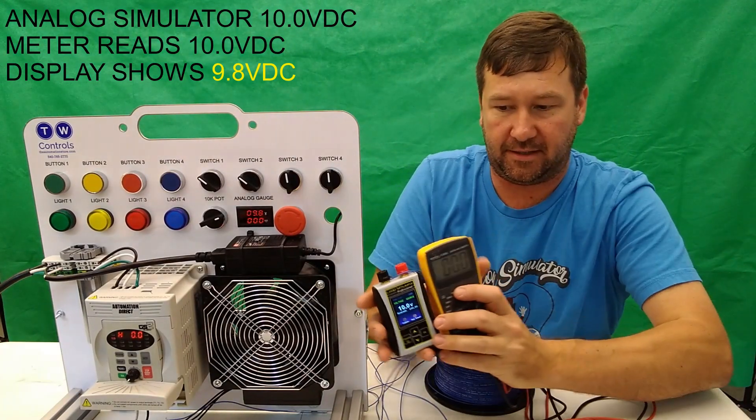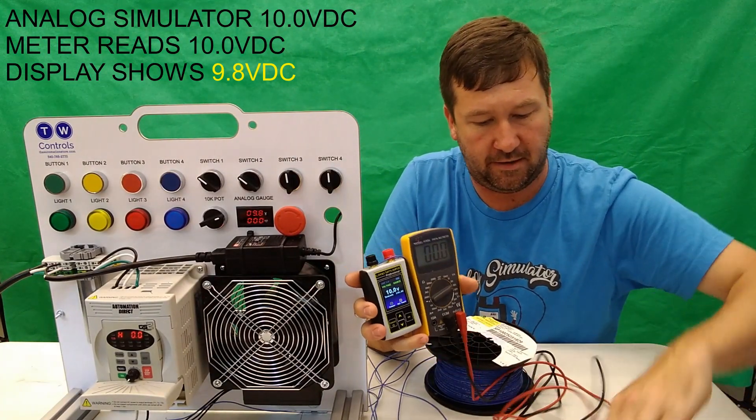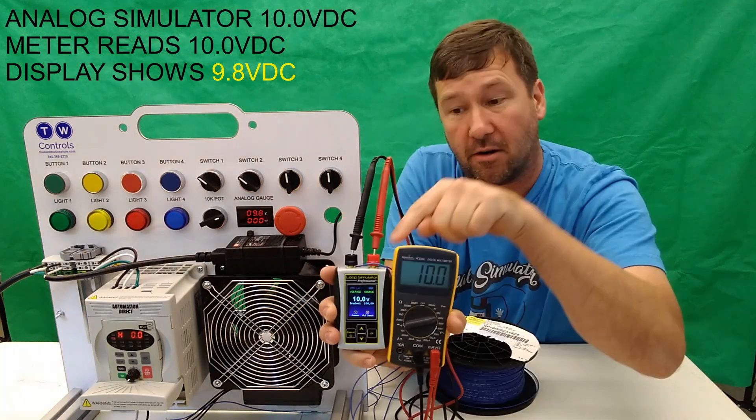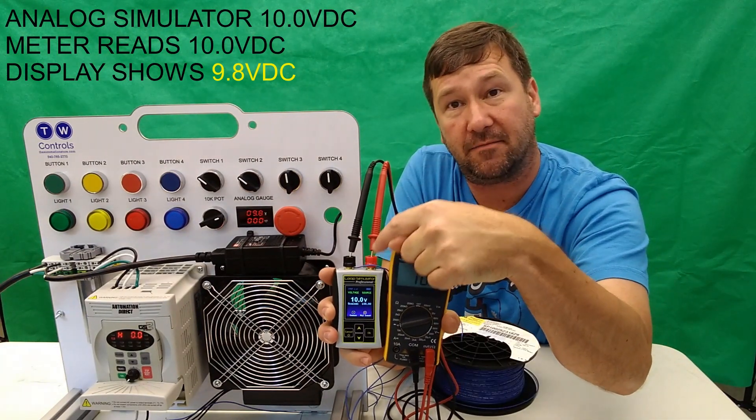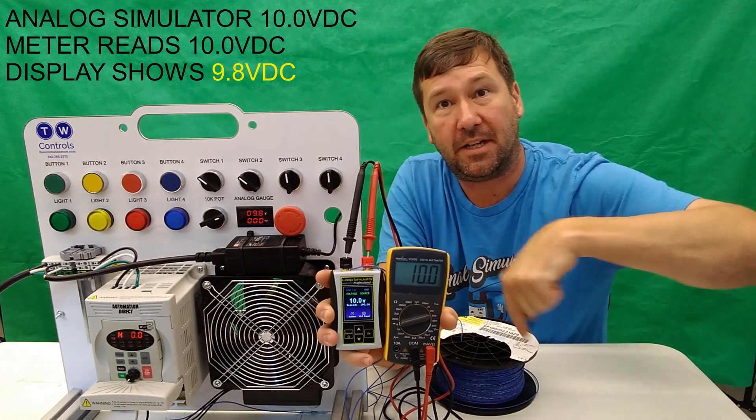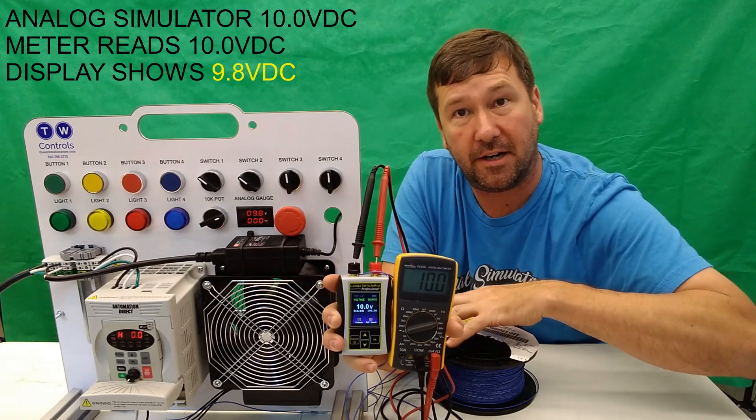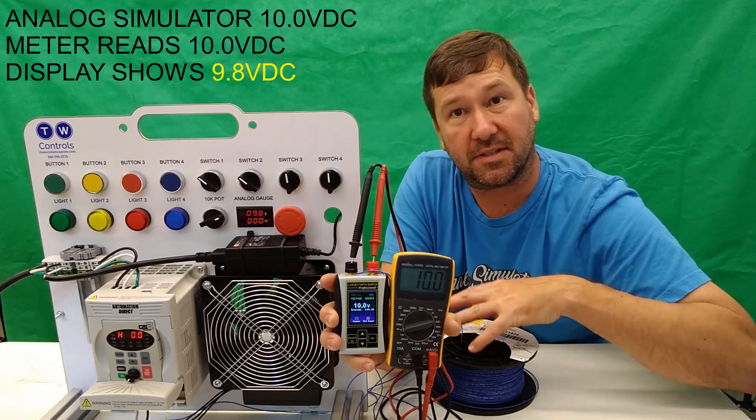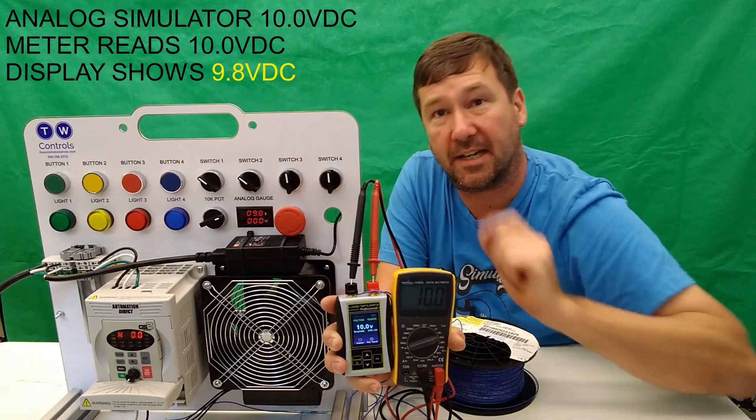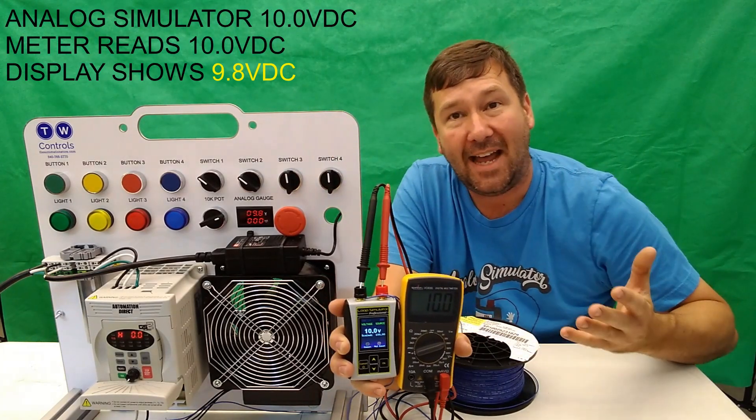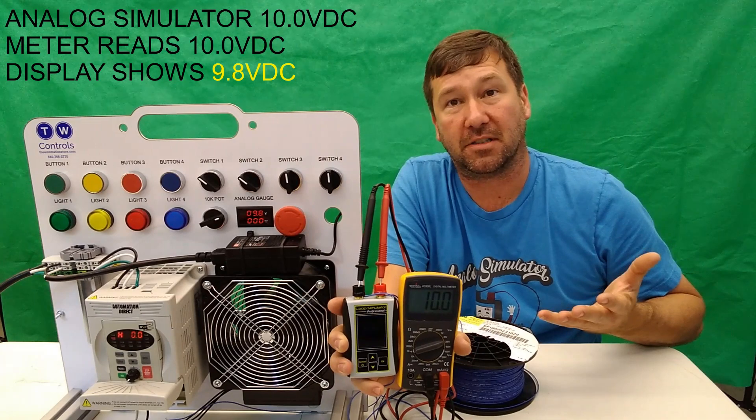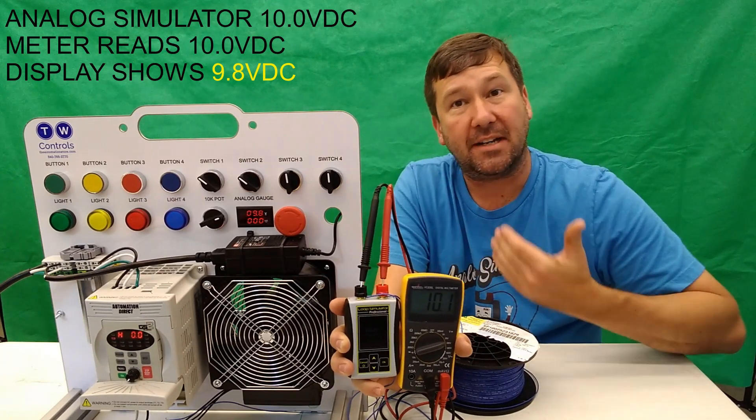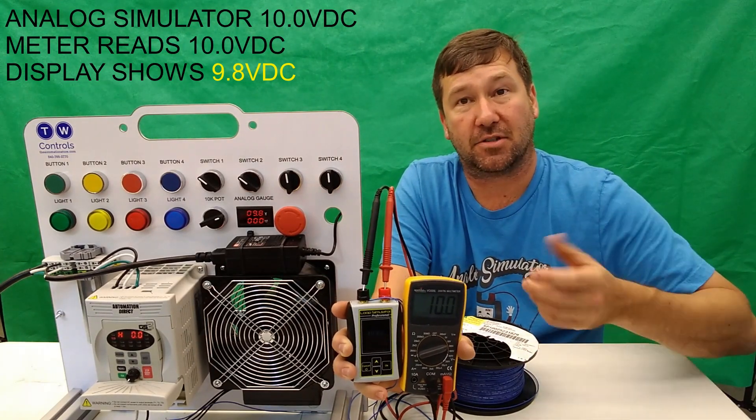Now just to verify that nothing is going wrong with our simulator, we're going to connect the meter. Our simulator is putting out 10 volt, but by the time we go through all of this wire here, it's creating enough resistance and voltage drop that we're only getting 9.8 volt to our meter. And that's the problem with a voltage signal is that over any amount of distance, you're going to have voltage drop.